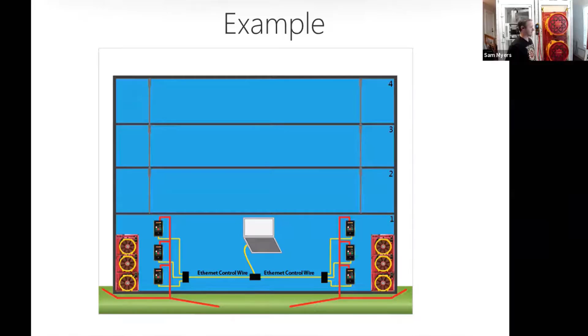And then coming off the blue, which, for a blower door test, usually for a single fan test, you usually don't do anything with this port just because it's reading your building pressure right there at the gauge. And for houses, that's okay. Usually, as long as you have all of your interior doors open, you're going to get that universal pressure throughout. But for buildings like this, we want to be able to take tubes and reference each floor to make sure that we are getting that desired pressure all the way throughout. So within your planning process, this is what I was talking about when running tubing. You want to be able to make sure you have a good pathway to do that.